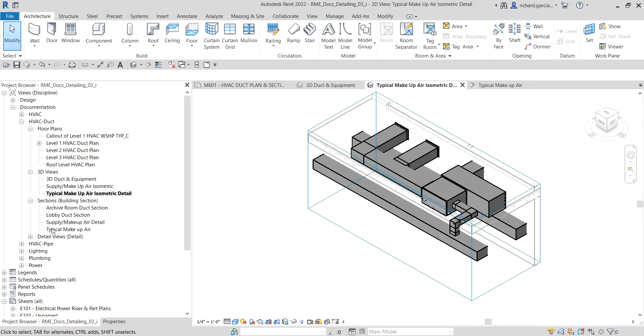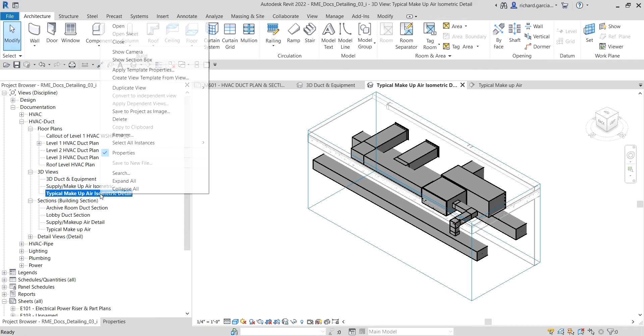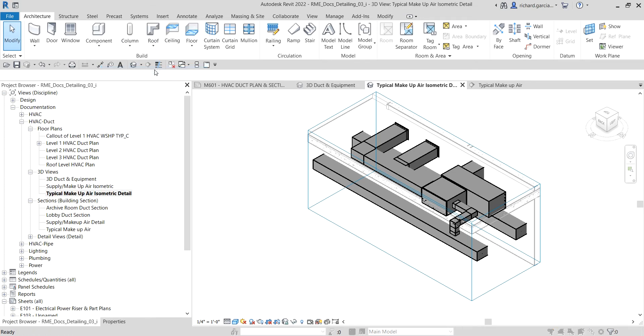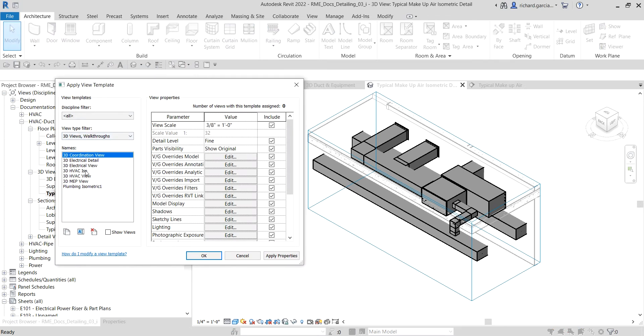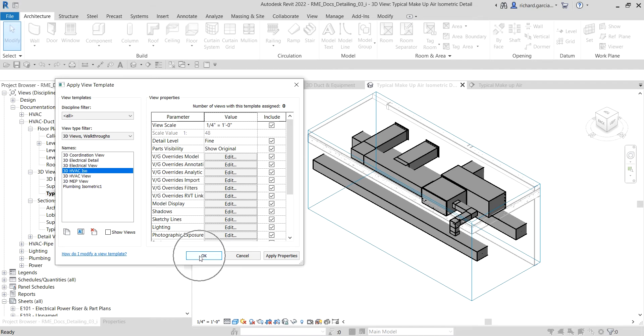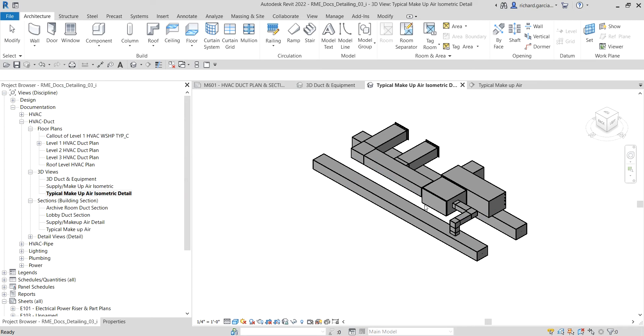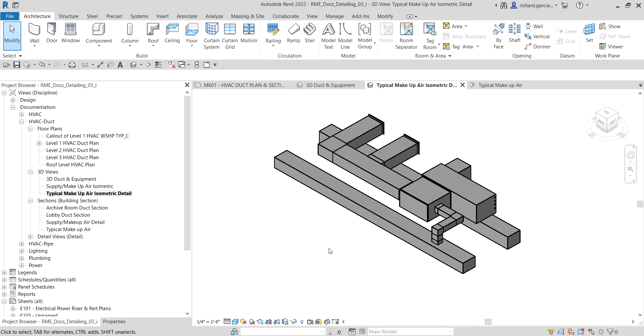The next step is to apply a view template. Right-click and select 'Apply Template Properties.' In the Apply View Template dialog box, look under 3D Views/Walkthrough and select '3D HVAC Isometric' (or ISO). Select OK. This will isolate the mechanical components by turning off the architectural components — now only the mechanical elements are visible.